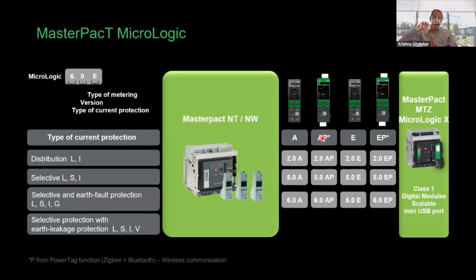So gone are the days you add multiple accessories, cabling, doing loop in, loop out, and then connecting to a gateway. You just put PAS 600, and all the AP and EP wireless trip units of MasterPact MTZ Active will communicate wirelessly to PAS gateways. The benefit of this architecture is, as you have seen, we have thermal sensors, we have PowerTag in the MCBs and other devices. All these devices can also connect to the PAS gateway, so that your installation becomes much more reliable and much more flexible, because you're avoiding all the wirings, and it can directly communicate to the PAS gateway, which has embedded drivers for this.